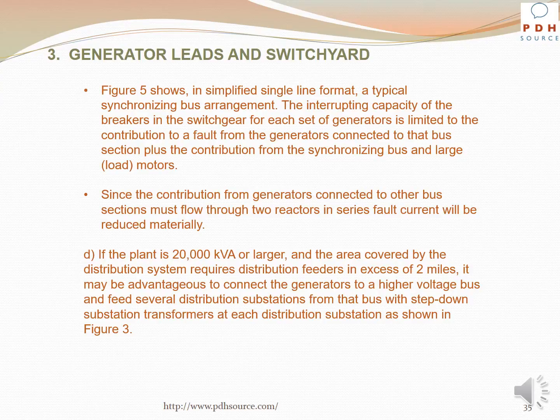If the plant is 20,000 kVA or larger and the area covered by the distribution system requires distribution feeders in excess of 2 miles, it may be advantageous to connect the generators to a higher voltage bus and feed several distribution substations from that bus with step-down substation transformers at each distribution substation, as indicated in Figure 3.